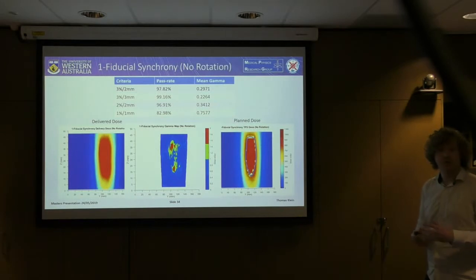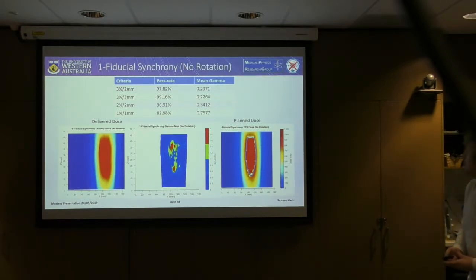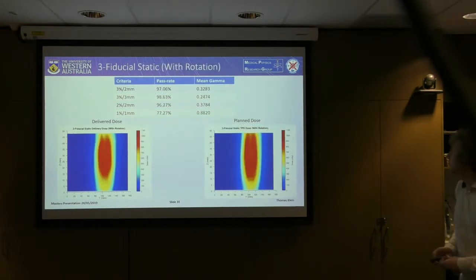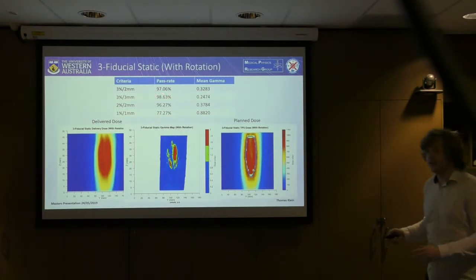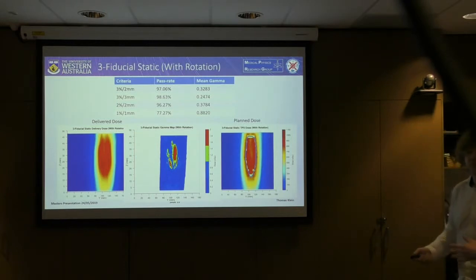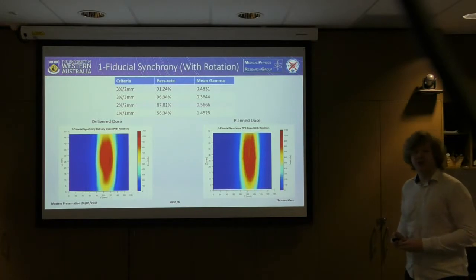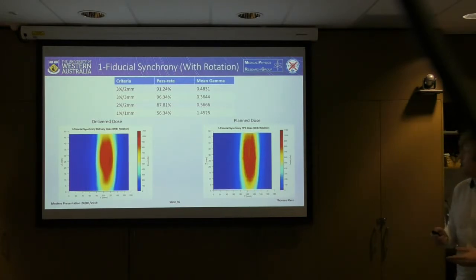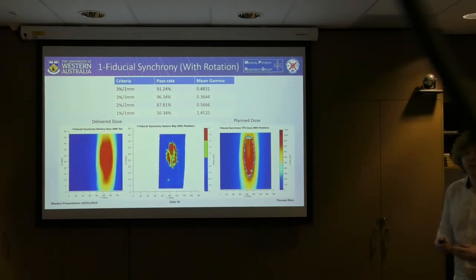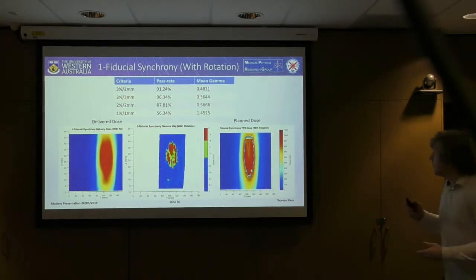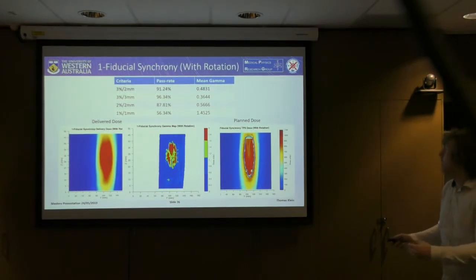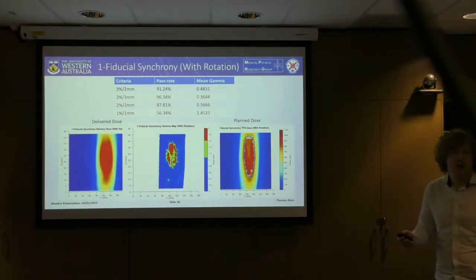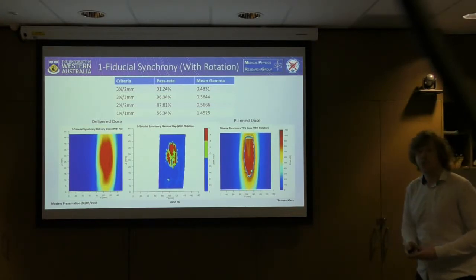I believe the three-fiducial system was attempting to correct for rotational corrections that didn't need to be made, effectively overcompensating and degrading the resulting dose distributions. For the phantom setup with rotation, the static delivery still showed agreement above the 95% cutoff. However, the one-fiducial Synchrony tracking with added left-right and anterior-posterior target motion was significantly degraded, because with one-fiducial tracking you cannot account for rotational errors. The three-fiducial Synchrony tracking could not be completed for this setup as it was exceeding the rotational tolerance of the system — meaning the error was too high to proceed — whereas the one-fiducial delivery, unaware of this error, was allowed to proceed with a consequently poor dose agreement.